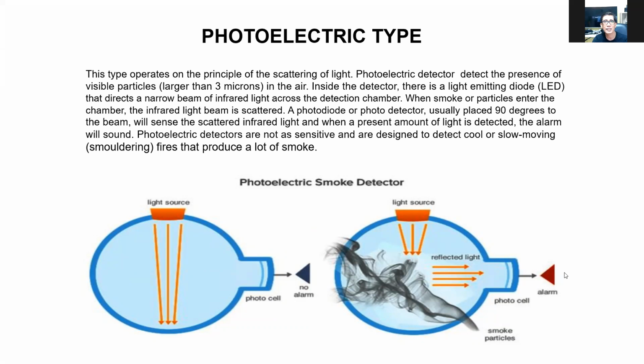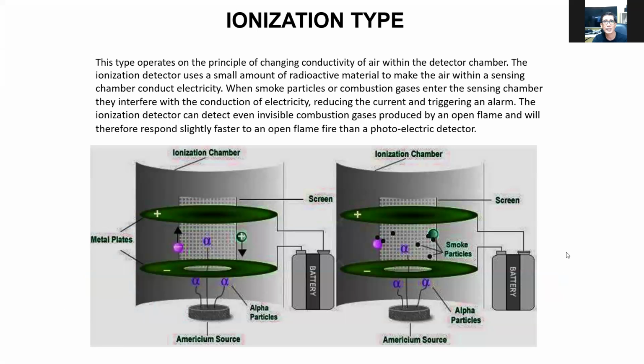Another one is the ionization type. This operates on the principle of the conductivity of air within the detector chamber. The ionization detector uses a small amount of radioactive material to make the air in the sensing chamber conduct electricity. When the combustion gases and smoke particles enter the sensing chamber, they interfere with the conduction of electricity, reducing the current and triggering an alarm. It is similar to the LED reflection to the alarm, but this time you are using ionization. If the smoke particles are in the middle of the ionization chamber, between the positive and negative poles, it will create an alarm.